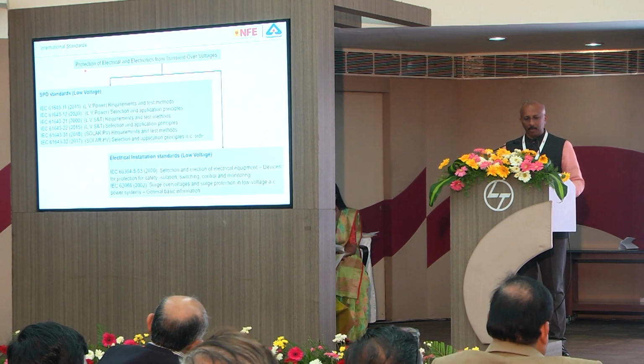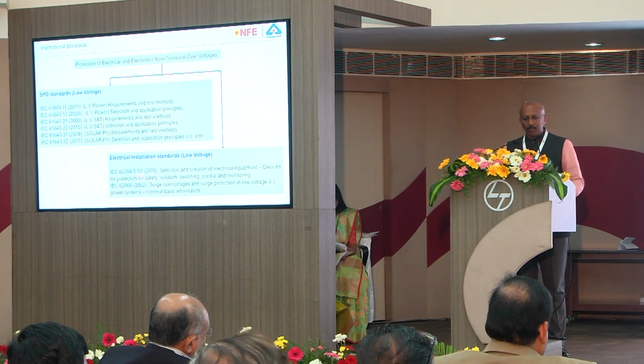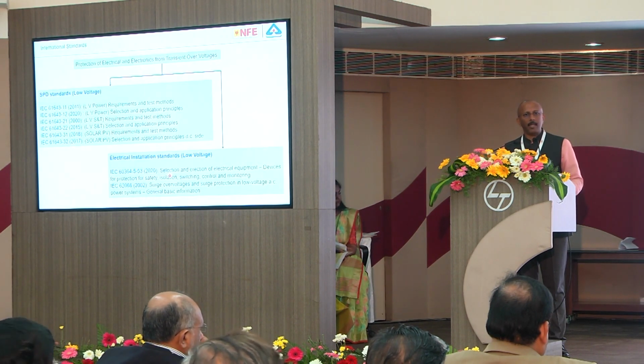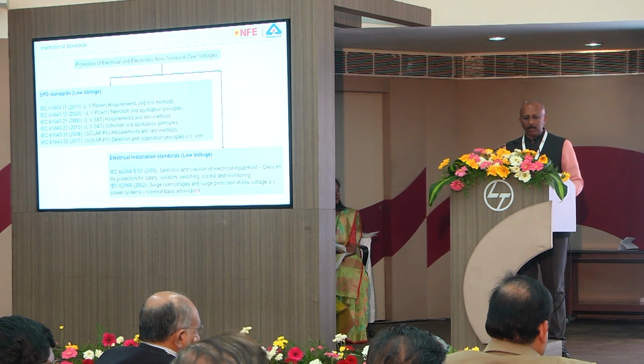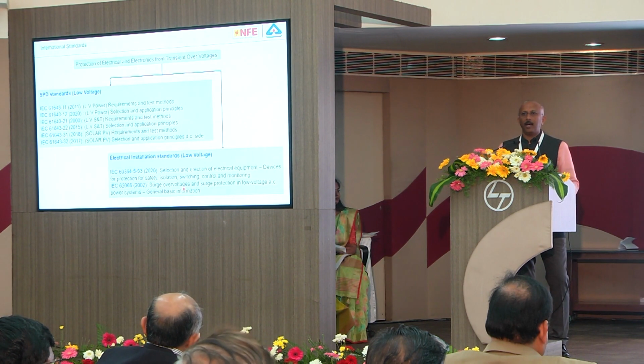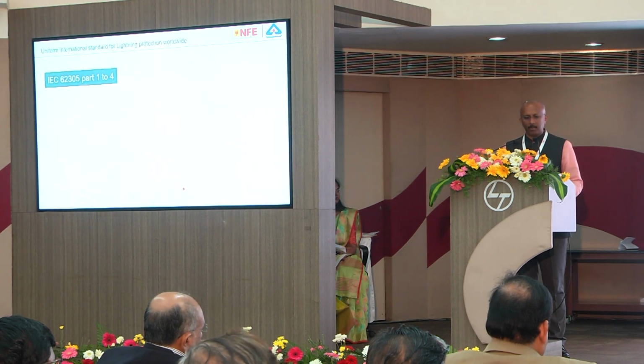an SPD appropriately. There are two standards, 60364-553, which is nothing but IS 732 or NEC part 1 section 13, and 62066. This is actually surge over voltage and surge protection in low voltage AC system for basic information, how in case of a lightning strike on the overhead line, how much current can be coupled into the building. Those informations are given in this particular standard.